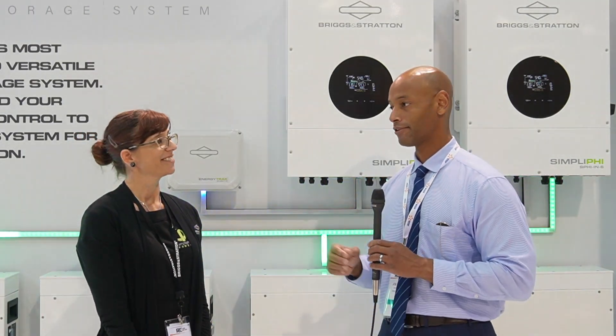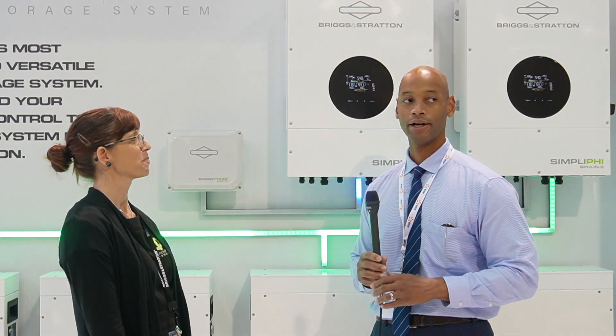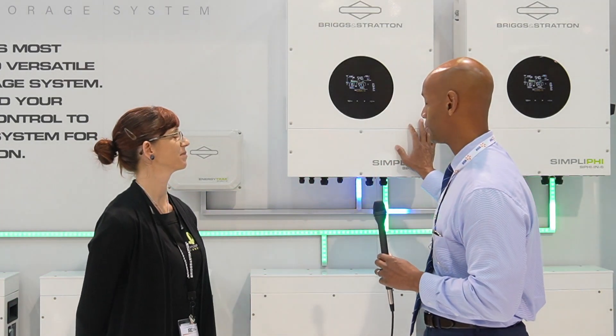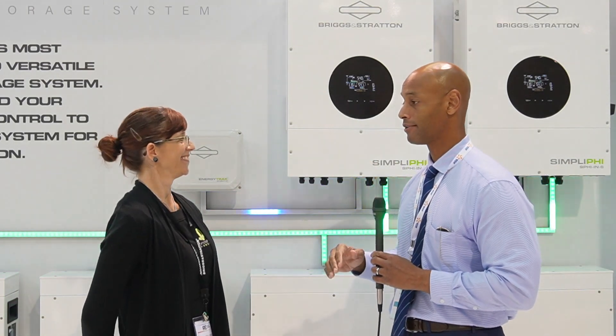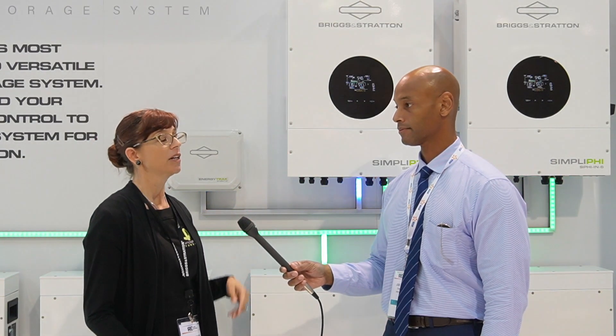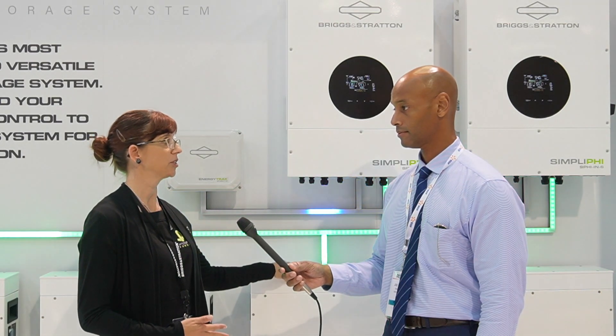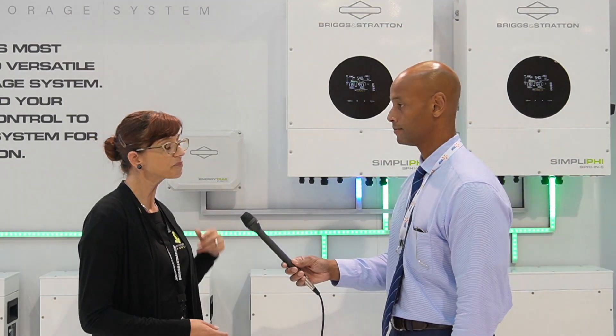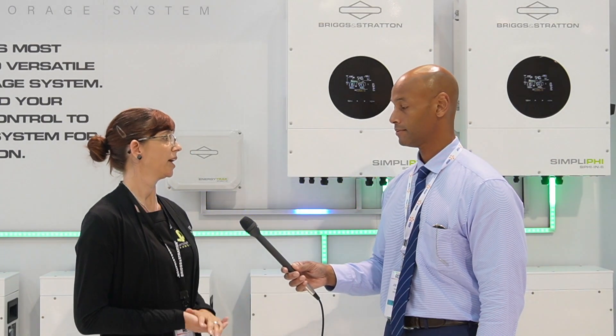Now one last question about generator support, because I know the audience is going to want to know. One of the nice things we see on some generator-compatible inverters is the ability for the inverter system or system controller to automatically start and stop the generator based on battery state of charge. Is that something you're going to be offering? I'm glad you asked — this inverter does have integrated automatic generator start. It will start a generator based on the voltage of the battery, which is settable. Additionally, it has rapid shutdown already integrated in. We work with APsystems, so there is a rapid shutdown relay built into the inverter. That rapid shutdown relay can be wired to an e-stop and it will disconnect the PV and also disconnect load.